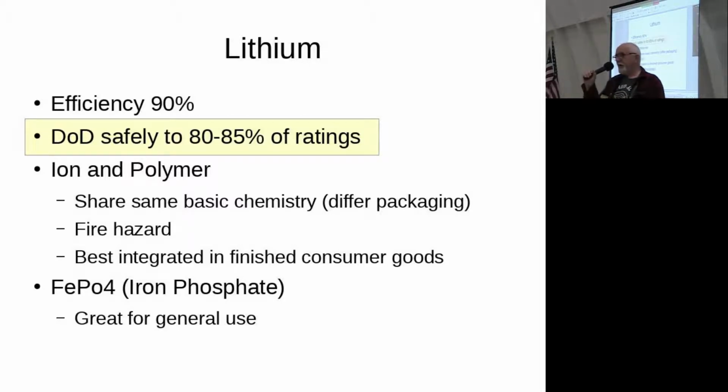And in fact, if you recharge your batteries, you don't have to charge them up to 100%. Because most of the heat that's generated in a battery happens when it's at low discharge levels and you're trying to get the remaining current out of it, or when you're recharging it and you're trying to get the topped off portion, the resistance goes up and you generate more heat in these batteries. So recharge them to 90% and don't discharge them below 80% and size the battery accordingly. In other words, spend a little extra money and get a little extra space and be kind to your battery and keep the heat down.